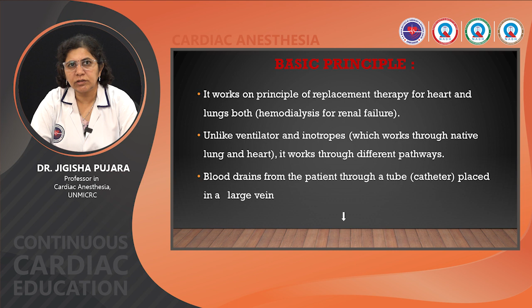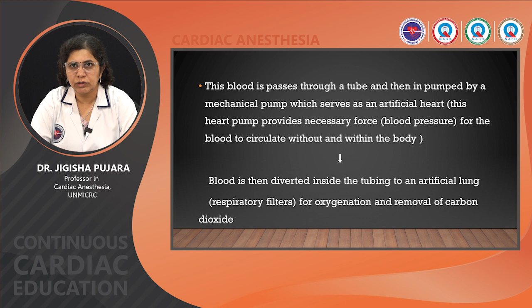Blood drains from the patient through tubes or catheters placed in a large vein. This blood passes through the tube and is pumped by a mechanical pump, a centrifugal pump, which serves as an artificial heart. This heart pump provides the necessary force, as blood pressure, for the blood to circulate without and within the body. This blood is then diverted inside the tubing to an artificial lung, a respiratory filter, for oxygenation and removal of carbon dioxide through the membrane.